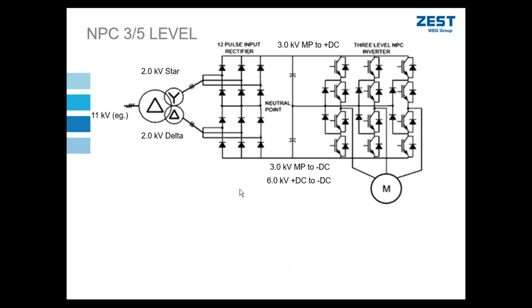Right, let's dig into this topology in a little bit more detail. We have a utility supply, just for an example, 11 kV, supplying our transformer primary. We split this transformer up into two secondaries for a 12 pulse solution. Right. This motor, I'm looking at a 4.16 kV solution here, a 4,160 volt output to the motor. Right. But I divide my secondary voltages into 2 kV each, because they each supply a series rectifier.